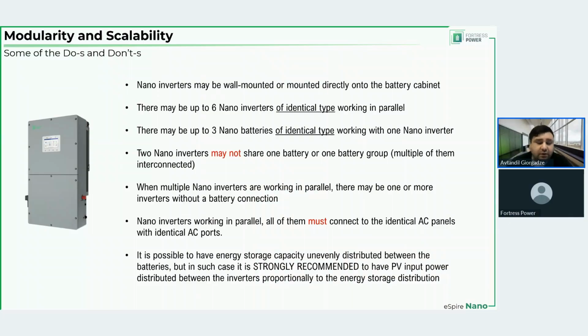You can have additional inverter that has no batteries whatsoever, and they just have PV connected to them. Now, that is technically battery ready, but you can run it without the battery indefinitely. One would ask, well, what's the benefit of having this inverter separately? Well, the benefit would be that if you were to connect AC coupled PV, right, or AC coupled inverter, we would only see the AC coupled inverter as the input to the smart ports of the existing nano inverters. But if you have additional inverter, first, it's battery ready, and secondly, you have the third, so to speak, AC coupled PV inverter, which is in reality nano inverter, acting like a string inverter, in the same communication chain as the other nano inverters with the batteries.